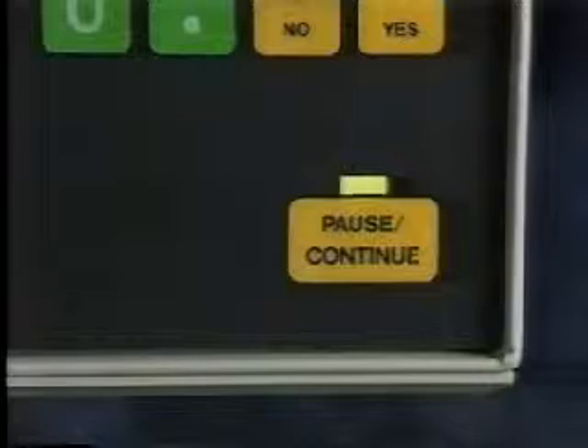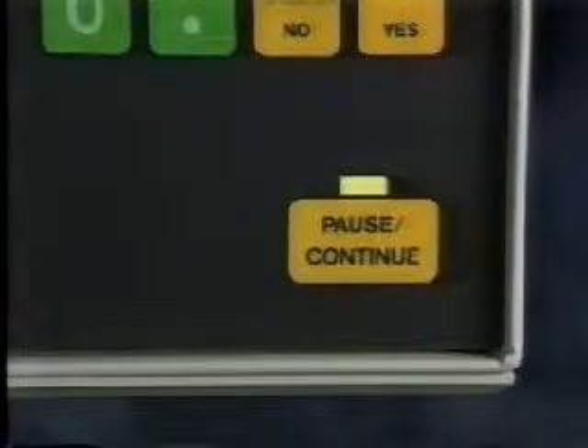Because system shutdown alarms require your immediate attention, they are indicated by a distinctive chime alarm, a flashing red alarm LED, and a flashing alarm message. When the pause LED is on steady, the alarm is still active. When the pause LED is flashing, the alarm condition has been cleared. Warning and operator attention alarms require you to be aware of the system's current condition and are indicated by an audio alarm and a flashing yellow warning LED.